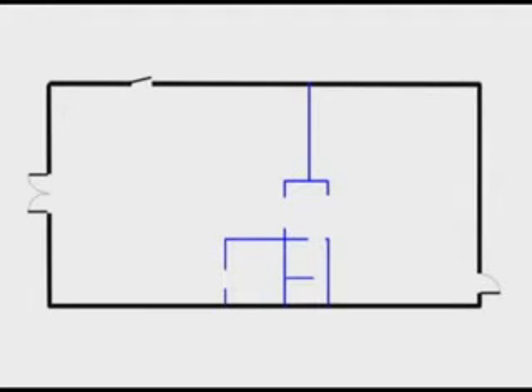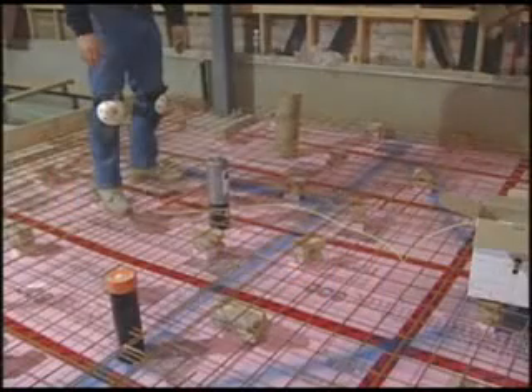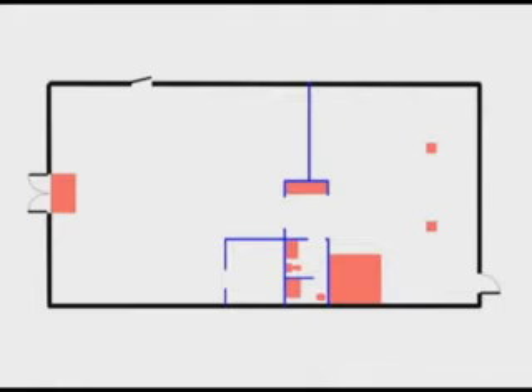Determine the limits of the surface that will be heated, the position of any future walls, partitions, and contraction joints, as well as any obstacles needing to be worked around, such as built-in furniture or any objects under which air cannot circulate freely. Use spray paint to trace the position of all these objects directly on the mesh. Since every room located over the slab has its own installation, verify all their measurements and recalculate the heating area of each one separately to be certain that these areas correspond to the cable sizes you've selected.